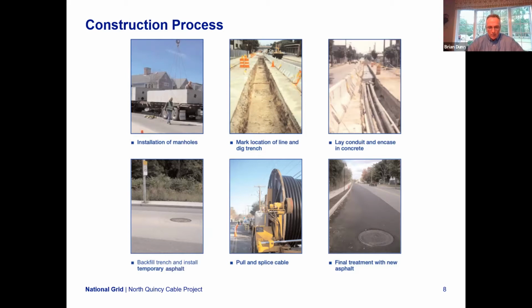After the duct bank and manhole system is in, we'll have setups in the roadway again, but these are fairly limited in duration, where they'll pull and splice the cable, set up just over the manholes. In the 3 miles there are 11 manholes - 2 of them off the roadway, so 9 manholes in the roadway. They're in pairs, so there's actually a total of 18. They'll set up over each one, pull the cables in, and splice them.